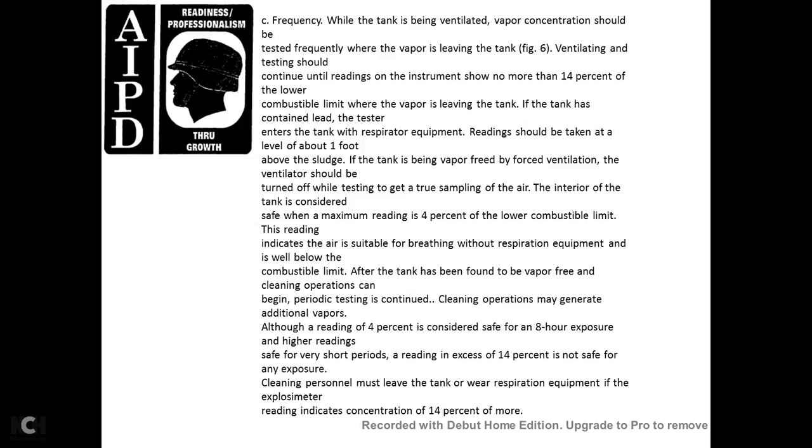If the tank can be entered safely with respiratory equipment, a reading should be taken at a level about one foot above the sludge. If the tank is being vapor-freed with forced ventilation, the ventilator should be turned off while testing to get a true sample of the air in the interior. The tank is considered safe when a maximum reading of 4% or lower of the combustible limit is achieved, indicating the air is suitable for working without respiratory equipment and is well below the combustible limit. After the tank has been found to be vapor-free and cleaning begins, periodic testing continues. The cleaning operation may generate additional vapors. Readings in excess of 14% of the lower combustible limit are not safe for any exposure. Cleaning personnel must leave the tank or wear respiratory equipment if the explosimeter reads 14% or more.